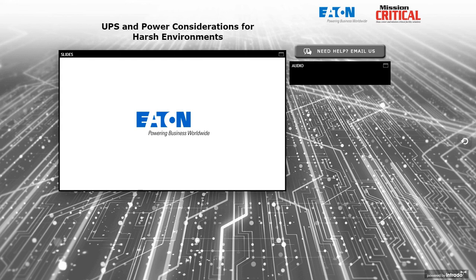So as a UPS purveyor, in general, we recognize that there'll be protection upstream of the bypass and probably protection in the form of fusing or breakers between the UPS and the critical loads. So we try to size the bypass fuses and the speed with which they operate to accommodate to where they would be the least likely fuses in the series there to open up. We don't want something in our UPS equipment to disconnect and cause a failure of the critical load unless it's absolutely necessary because, let's say, of a bolted fault or an extended overload condition.